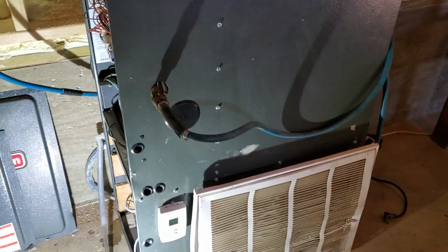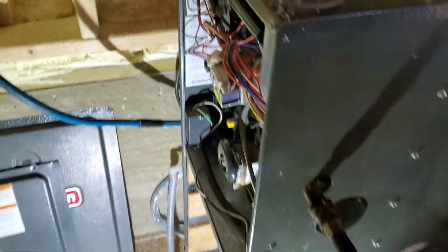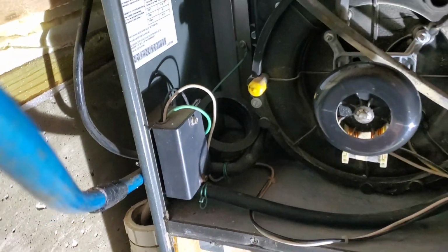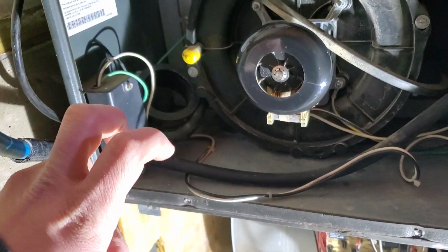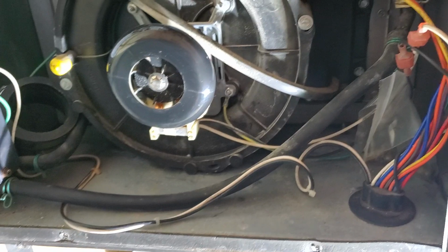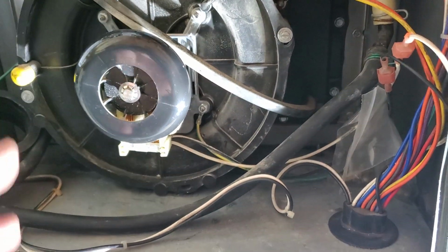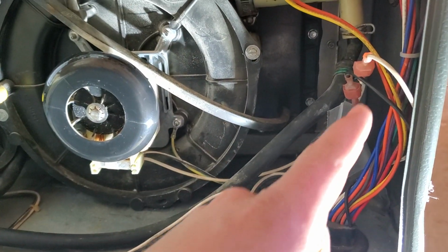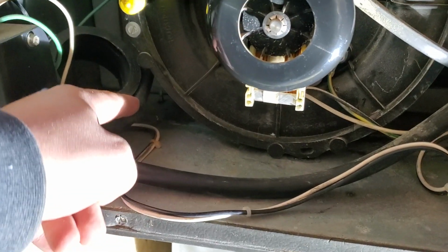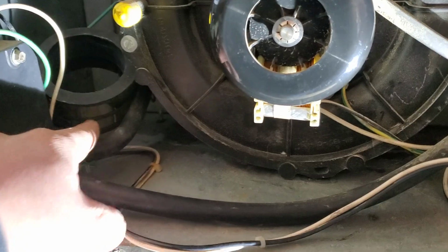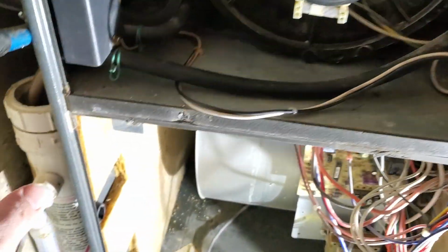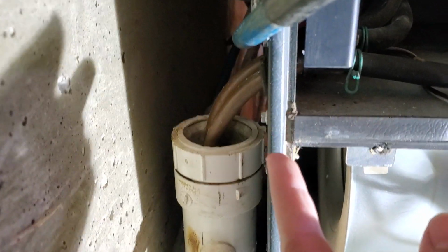All right, the last thing you're going to have to deal with is the condensate. So all high efficiency furnaces are condensing gas furnaces, meaning that they produce condensate when they run. So moisture will come through this tube and this tube right here, which comes off of the secondary heat exchanger back behind this blower, and that runs into what should be a trap on the side of the furnace.